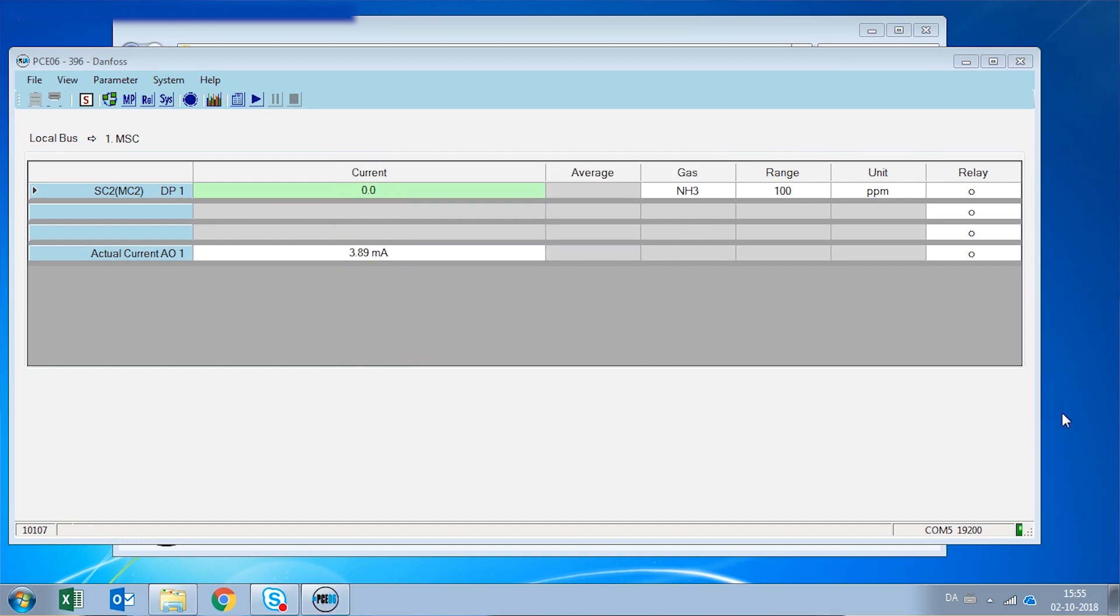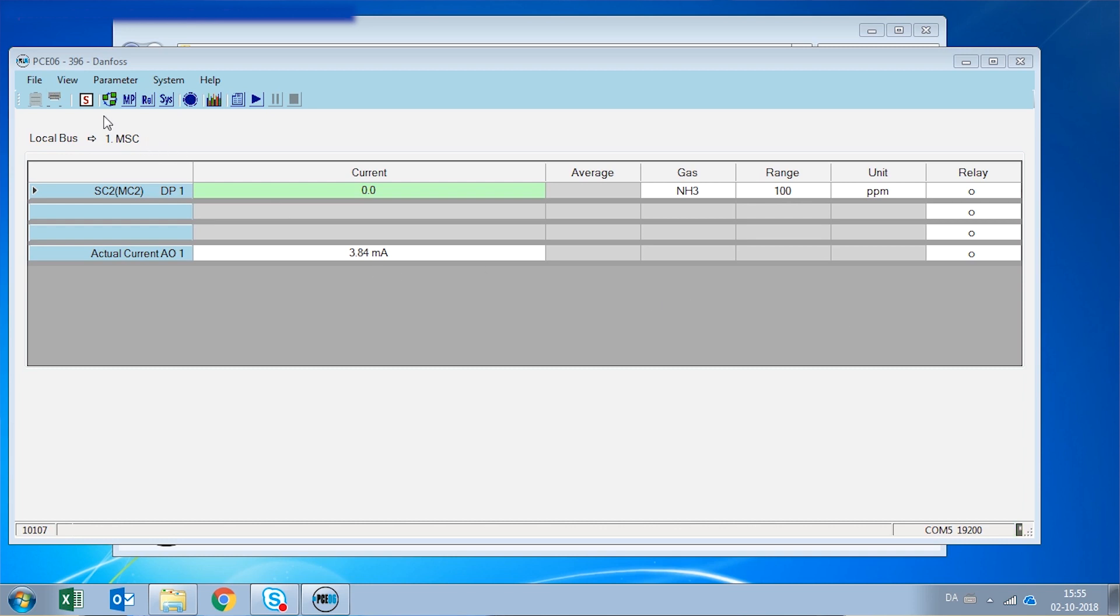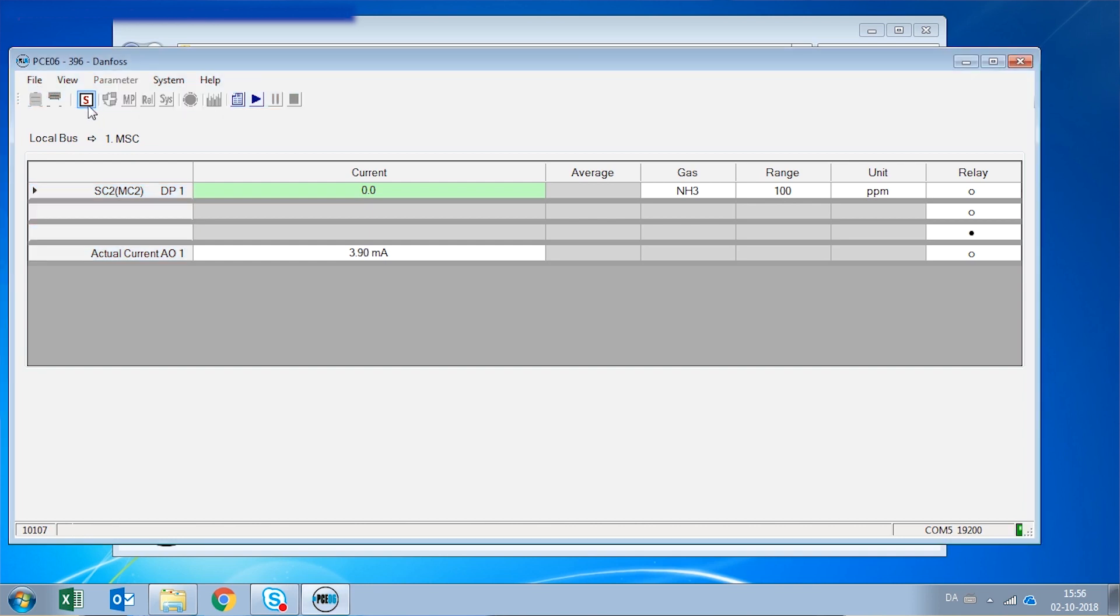Once we have finished using our PC tool and we have completed the changes or the calibration that we needed to do, we will need to remove the service mode from that gas detector. In order to do that, we are going to click again the button on the top left with the S. Once the service mode is off, you can see that the buttons to the right are not enabled anymore, only the one to do recording.